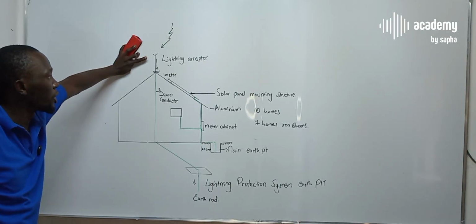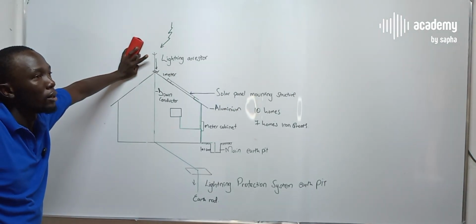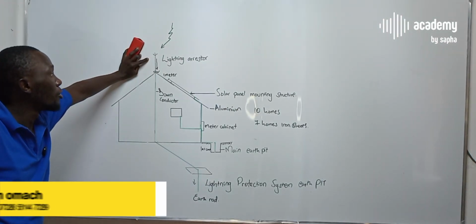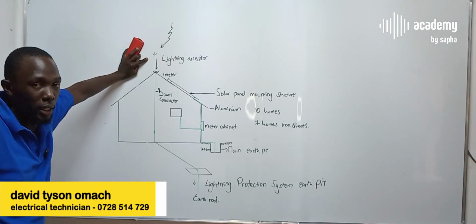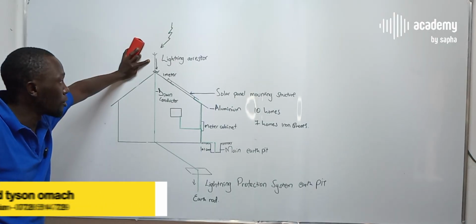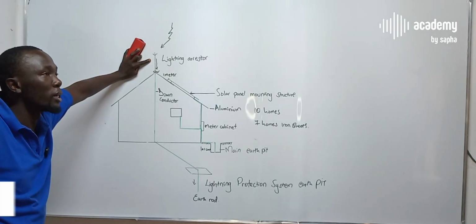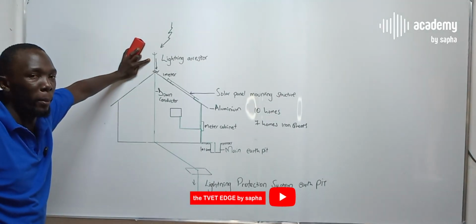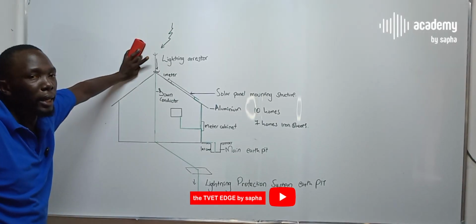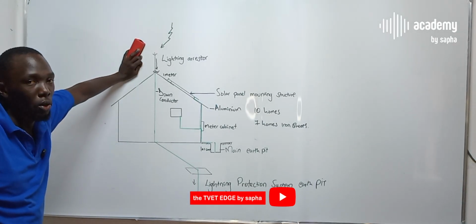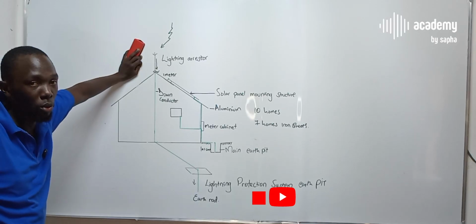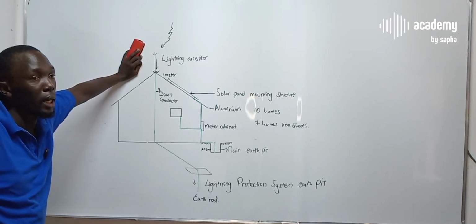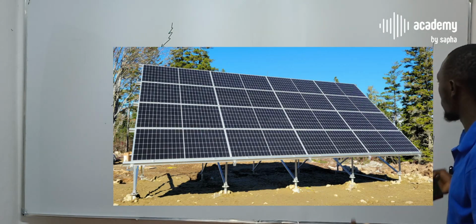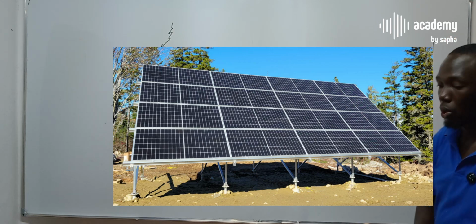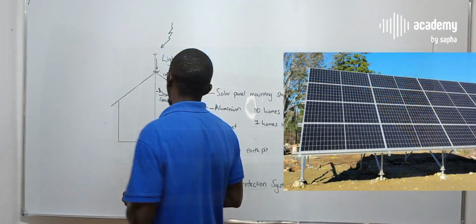Number one, whenever you're introducing a lightning arrestor, it has to be far from the structure you are trying to protect. If it has to be on the roof, there should be a safe distance of 1 meter plus between the lightning arrestor and any other metallic or conducting components on that roof, to avoid arc flash and other potential faults. That way you'll have protected your system in the recommended ways as per regulations.